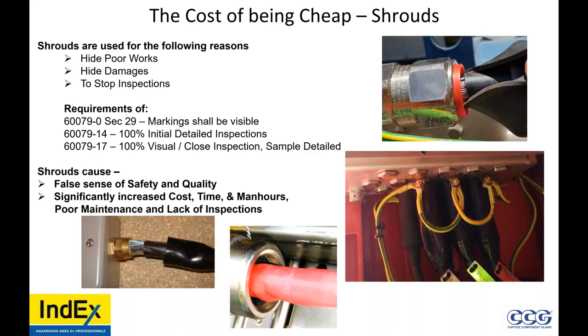And -17, you have to have 100% visual or close inspection and sample detailed inspection. How are you doing 100% visual inspection when you walk by if you can't visually see the gland? You don't know what's going on with it. Well, we inspected it 5 years ago. Okay, and what's happened since then? So shrouds cause a false sense of safety and quality. They significantly increase cost and time and man hours, poor maintenance, and lack of inspections.